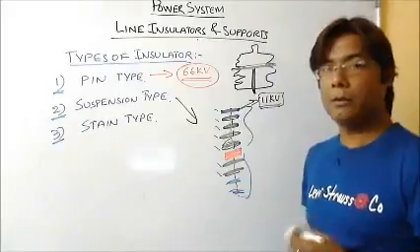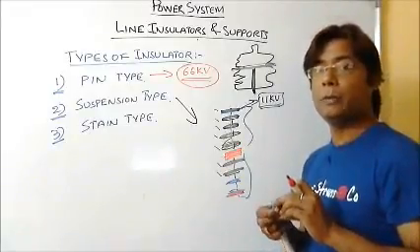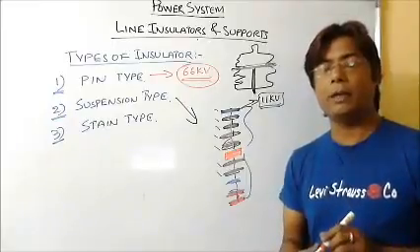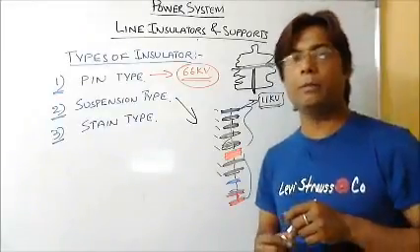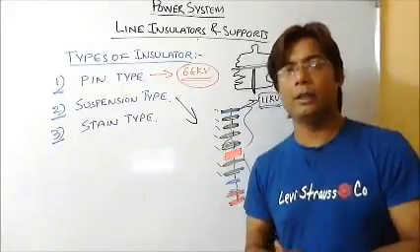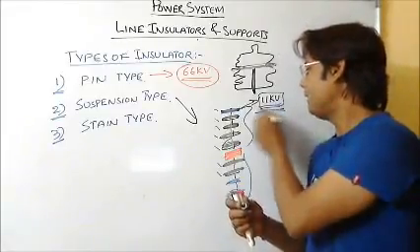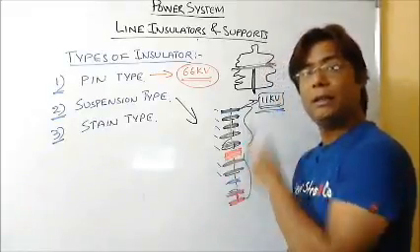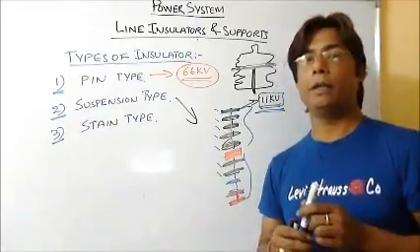It is also useful in future expansion. If this line is previously 110 kilovolts and is to be increased to 121 kilovolts, I can merely add one more disc, and the total string becomes suitable for 121 kilovolts. So there is a possibility of addition and deletion of discs such that the voltage increases or decreases in the conductor. These three properties are very important: every disc has 11 kilovolt, a faulty disc can be changed from any part, and discs can be added or deleted to get the desired voltage value.